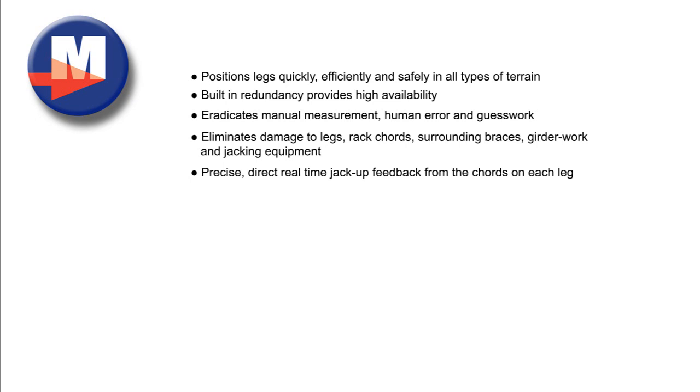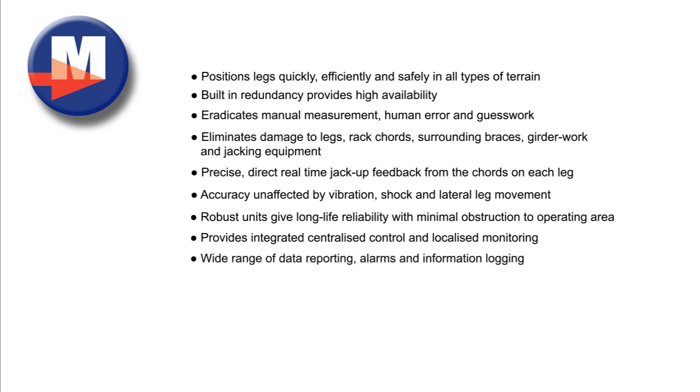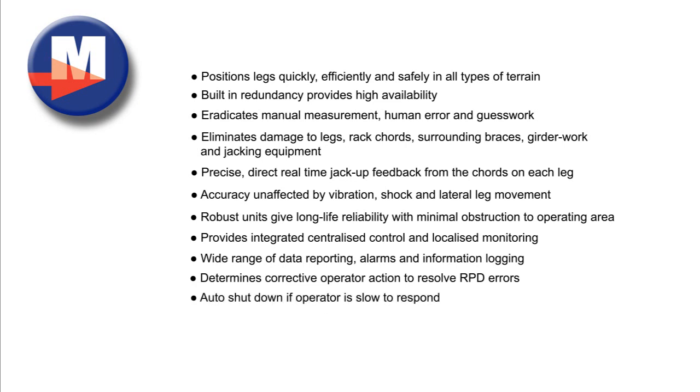Precise, direct, real-time jack-up feedback from the chords on each leg. Accuracy unaffected by vibration, shock and lateral leg movement. Robust units give long-life reliability with minimal obstruction to the operating area. Provides integrated centralized control and localized monitoring. Wide range of data reporting, alarms and information logging. Determines corrective operator action to resolve RPD errors. Auto shutdown if operator is slow to respond.